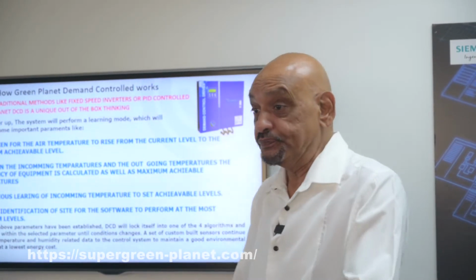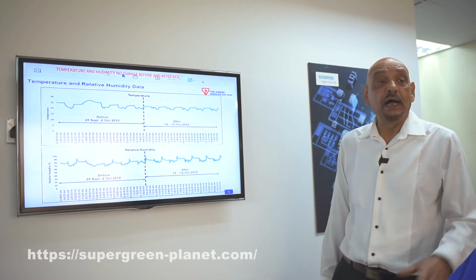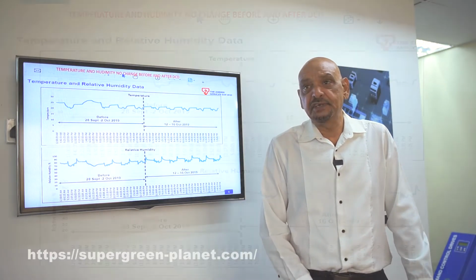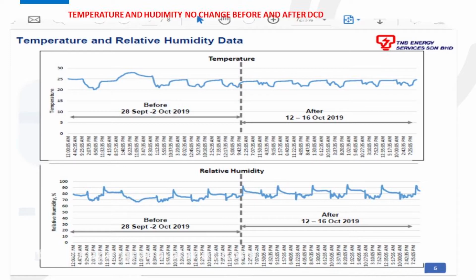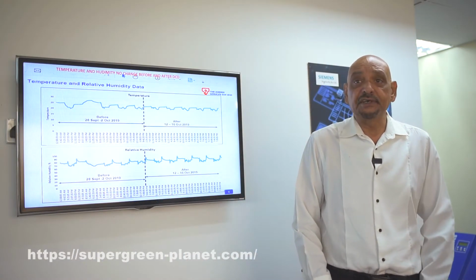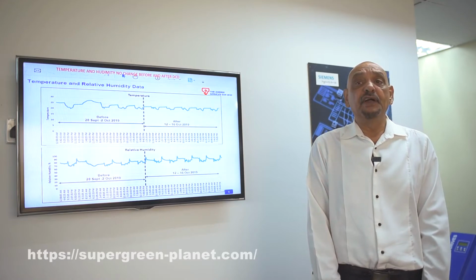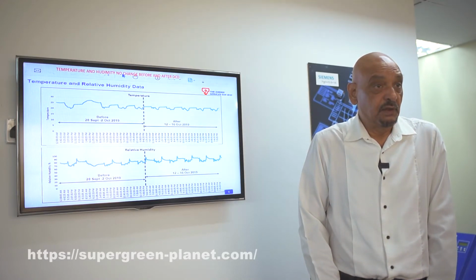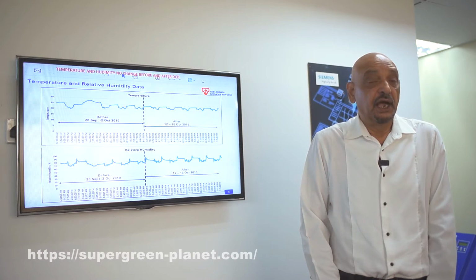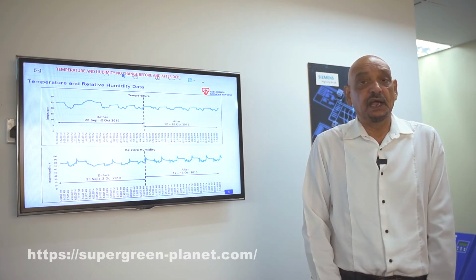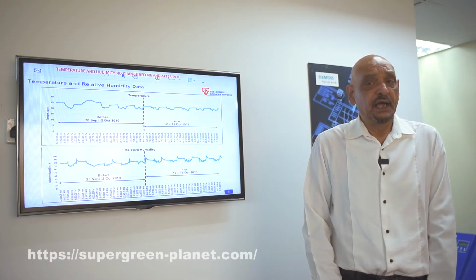Apart from that, I would give you an example of a test done by a subsidiary of our national energy grid. We call it Tenaga Nasional here. And they have done tests, and the results were very, very encouraging. Now, the test was done in a mall in a very, very high demand location with very, very long ducts, and temperature sensors were placed at the end of the longest duct and other areas.